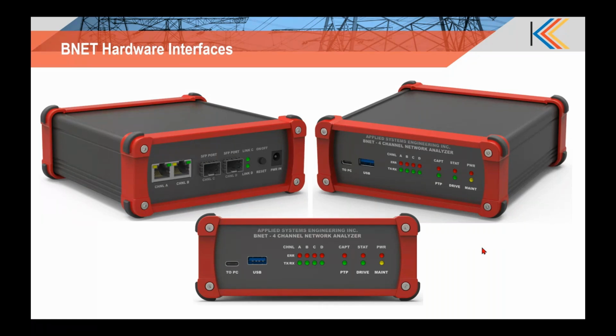A question I received quite frequently at a recent conference I attended is: is BNET expensive compared to the standard test set price? Actually, no. If you look at the price of other process bus products in the market, BNET will be much less. We want all technicians to have the capability to analyze the process bus because if we switch to 61850 digital substations, then most of the analysis and troubleshooting that you do in the DNP3 substations will have to be done on 61850 as well, right?